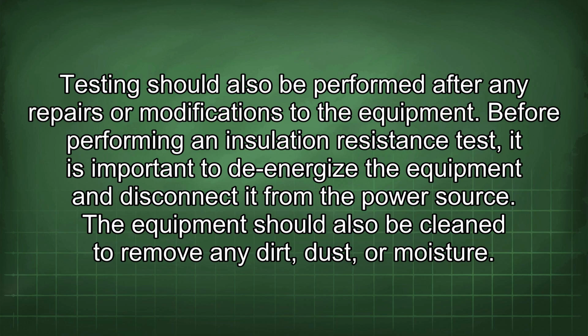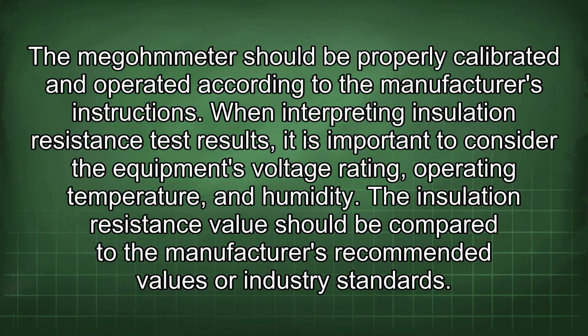Before performing an insulation resistance test, it is important to de-energize the equipment and disconnect it from the power source. The equipment should also be cleaned to remove any dirt, dust, or moisture. The megohmmeter should be properly calibrated and operated according to the manufacturer's instructions.